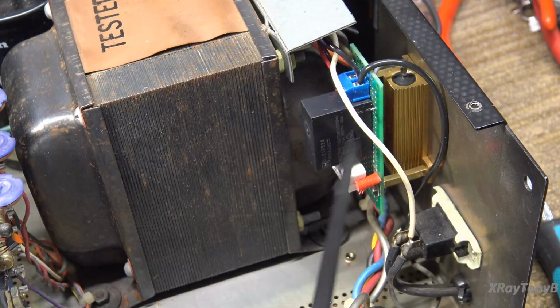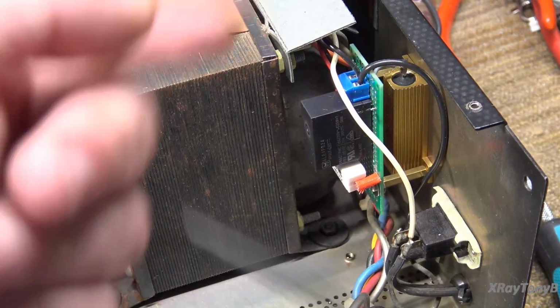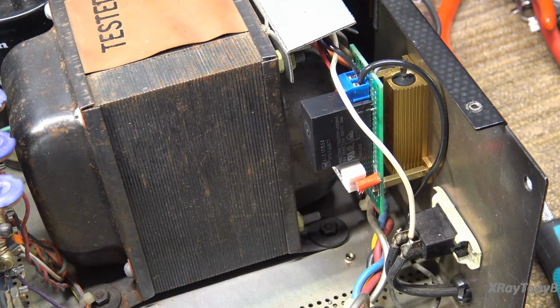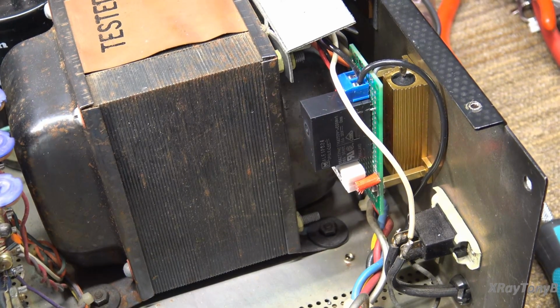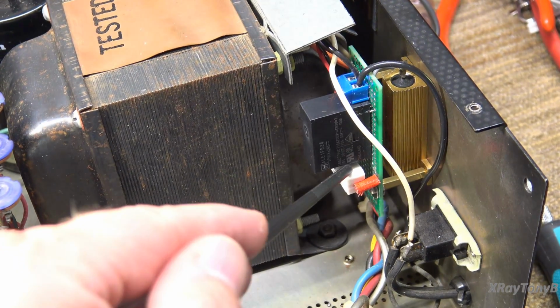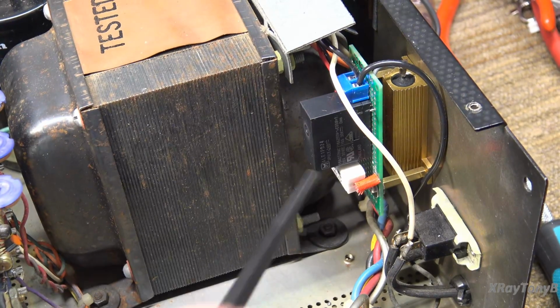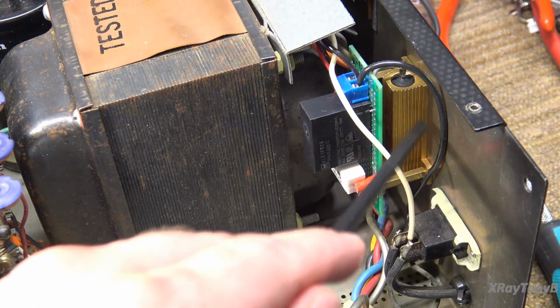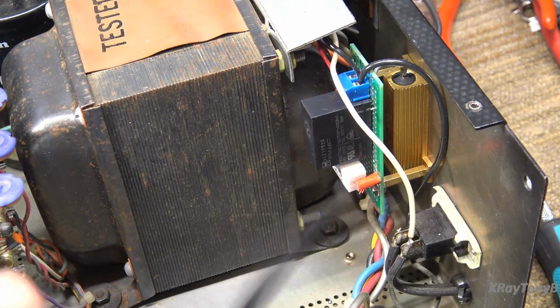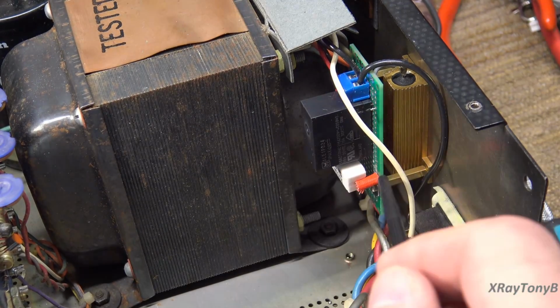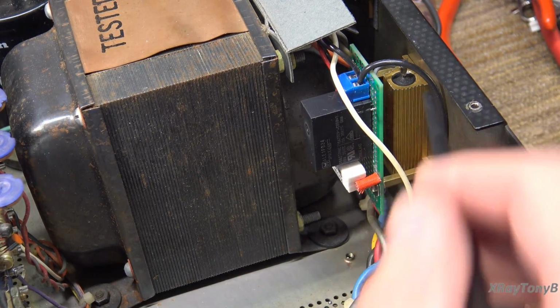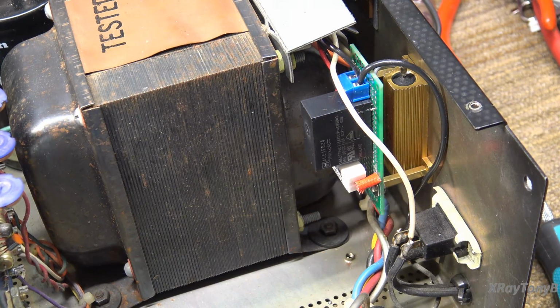If the capacitors are not charged up to the level they need to be, this will not pull in. It's a self-correcting circuit, so you don't need to worry about how long it takes to come in. It'll take as long as it needs for the voltage to come up before this comes in. And you don't need to worry about how much voltage drop there is across this, because by its nature, when the voltage is up to that level, the current is reduced, which means the voltage drop across this resistor is reduced, which means you're not shunting out that big of a voltage.